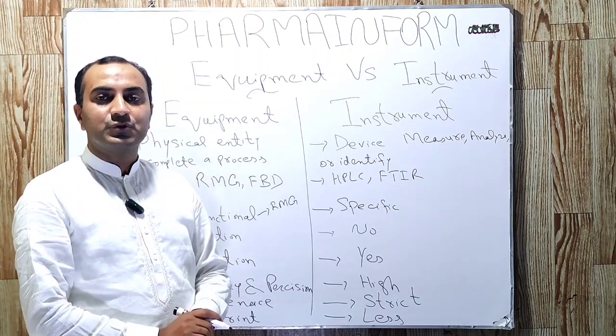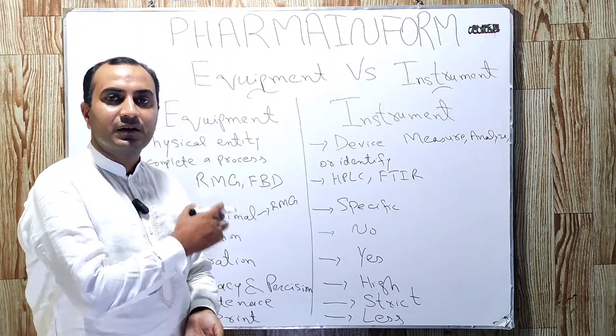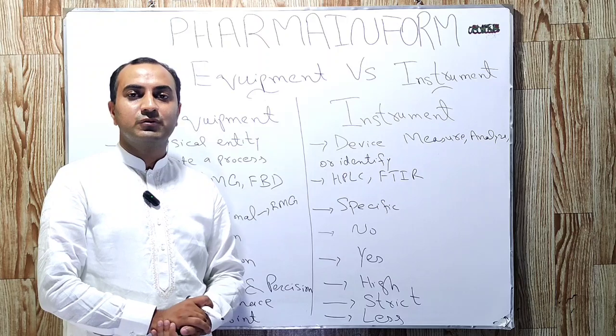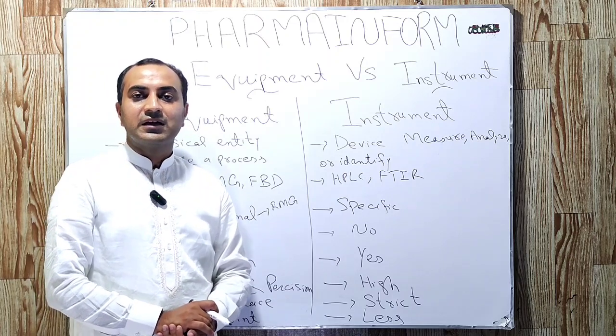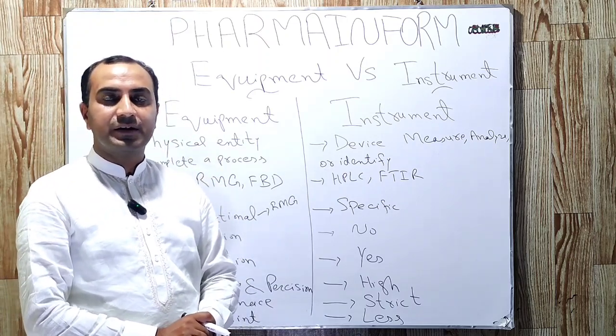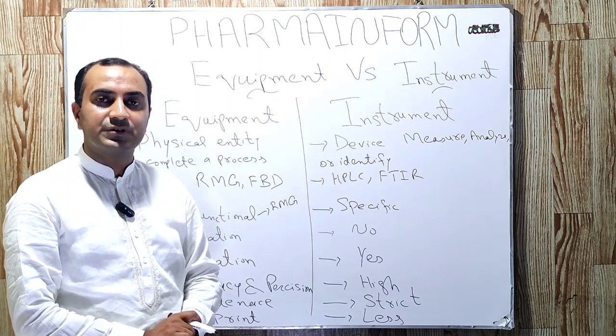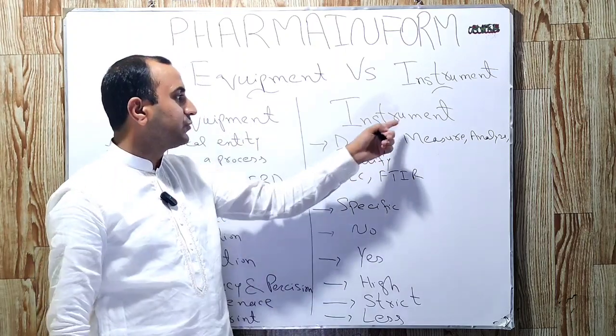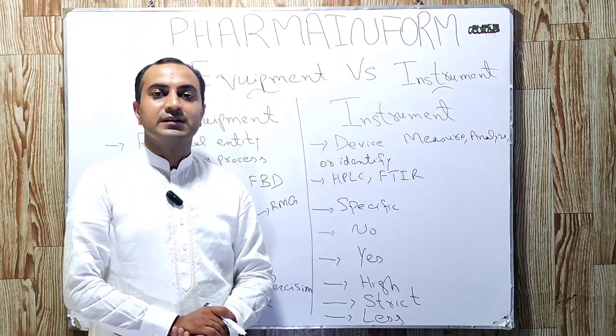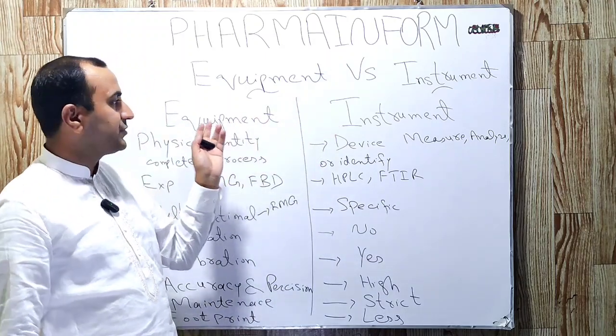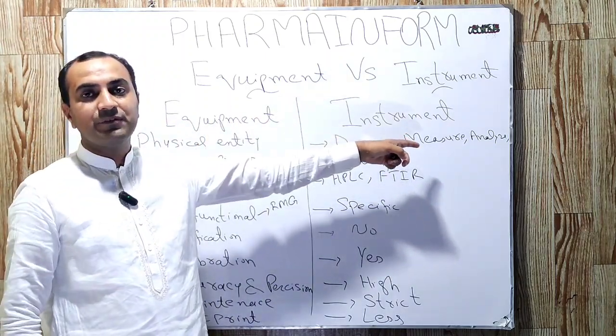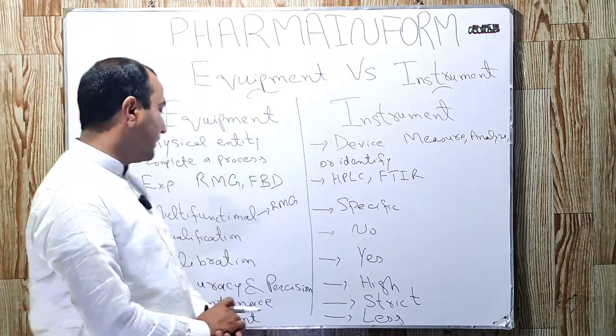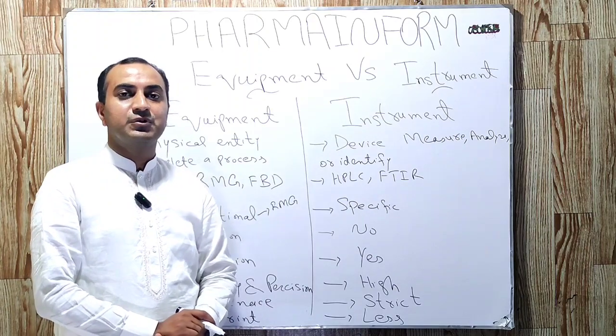The next difference is qualification and calibration. For equipment, we use qualification — equipment is always qualified and the process of qualification applies to equipment. In the same way, the process of calibration is used for instruments, and the term calibration is not used for equipment.